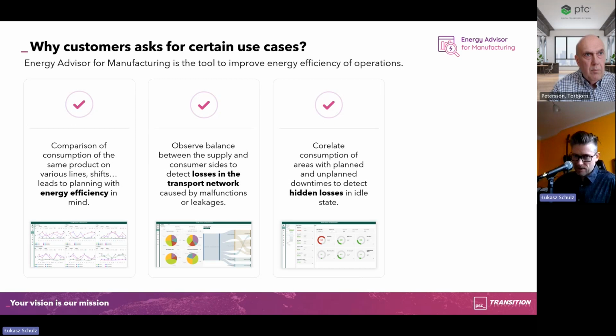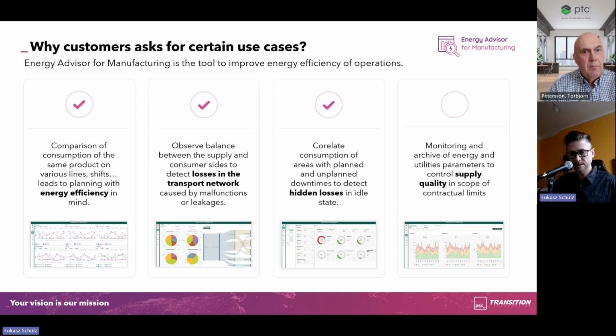What also happens, even with the most advanced customers we deal with, is unknown losses during shutdown. I know a customer who had heating on the whole year, whether it was hot or cold outside, always on. No one cared much about this—it was somewhere in the HVAC system. We can set alerts on it and compare: this line is shut down, it should not consume; this plant has a holiday break, it should not consume this much. It's important to understand this and find and cut those losses.